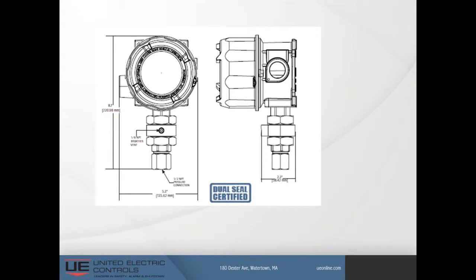The one thing I want to remind you guys of, that we're seeing quite a bit as I travel across the country, is the requirement for dual seal being really predominant today. In Canada, you can't sell anything today without a dual seal. This whole dual seal scenario comes from the mandate from NFPA and the National Electric Code to contain flammable or combustible materials and vent them to atmosphere so that they don't make their way into the enclosure and then down to the control room via conduit or a raceway.